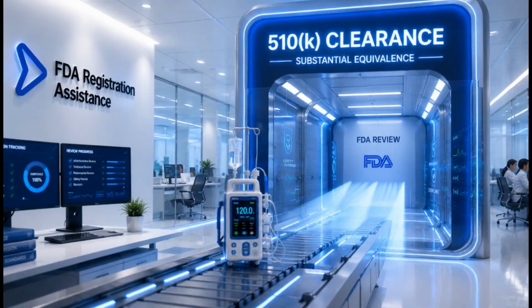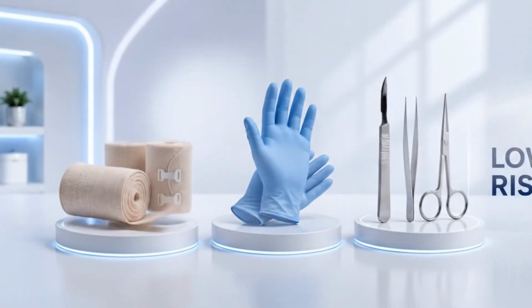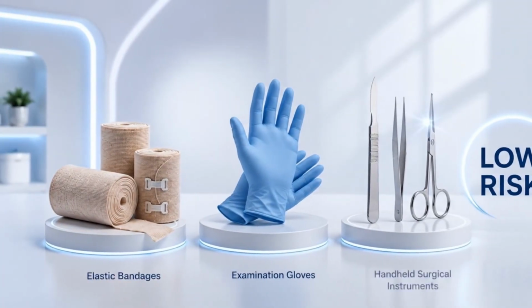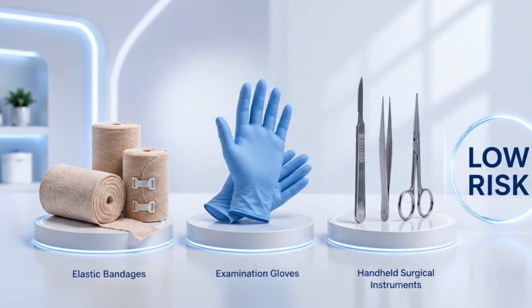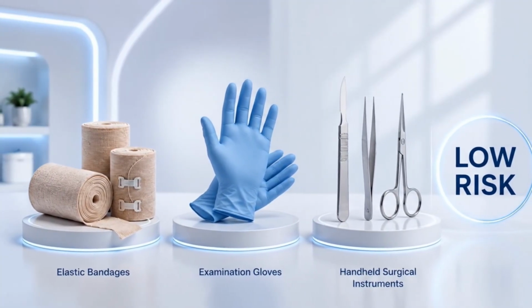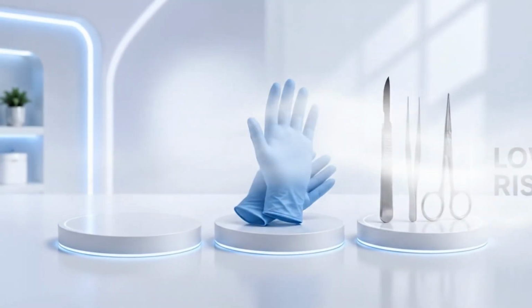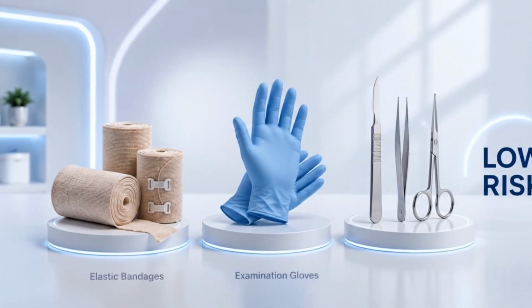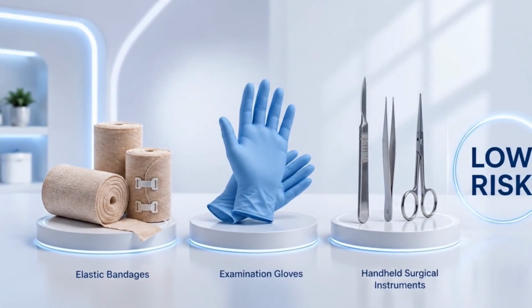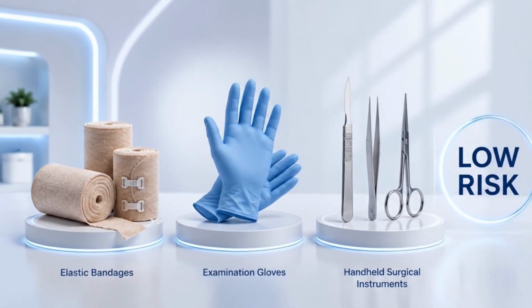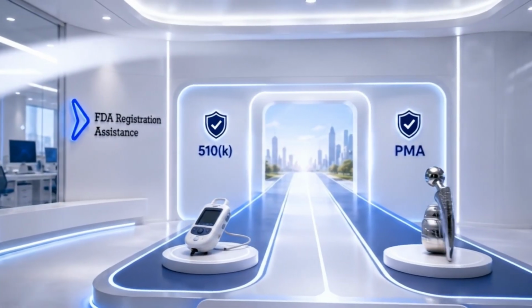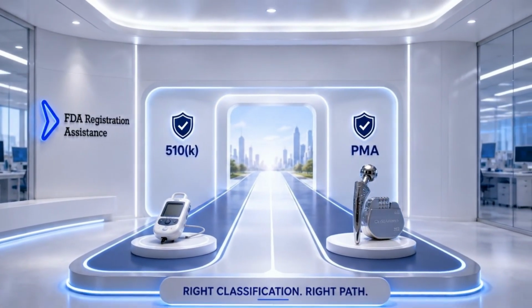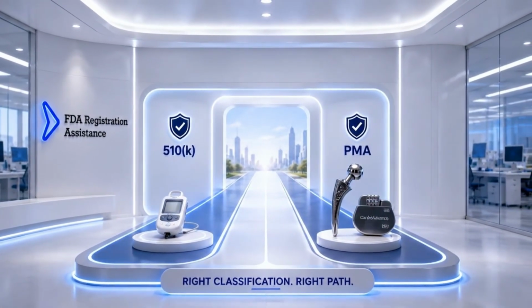Class 1 devices are considered low-risk medical devices. These products are subject to general FDA controls, but usually face fewer regulatory requirements than higher-risk devices. Examples may include manual surgical instruments, elastic bandages, examination gloves, and certain basic mobility aids. Many Class 1 devices are exempt from FDA 510(k) pre-market notification requirements.